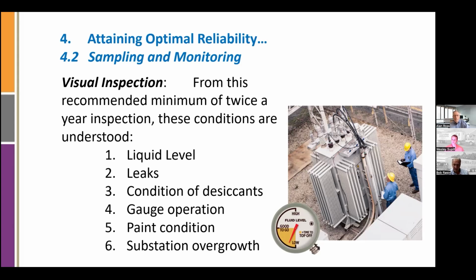When these radiator tubes become breached, the transformer is no longer cooling. You may not even see it on the gauge. The gauge could be elevated above the liquid level once it drops below the fins. Substation overgrowth.